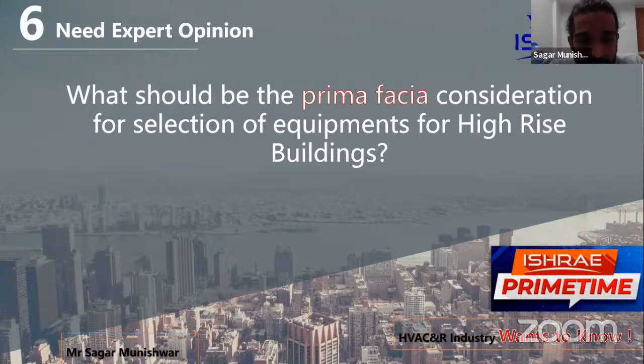So like I mentioned about chillers, when you go high rise, you need to select a chiller which can take that operating pressure. You need to have those valves in the line which can take the pressure. Again, a chilled water system is a closed loop system, so you will not have an issue per se of the pressure acting on the valve. But yes, when your system shuts down, the entire static load will come on those valves. And if you have a building which is 150 meters in height, you need valves of PN20 or PN25 rating to take care of that. Similar thing with the chillers.